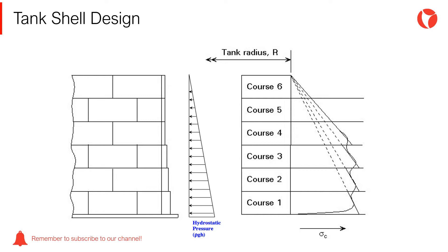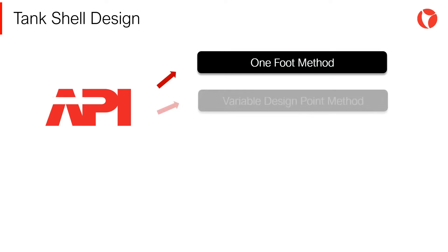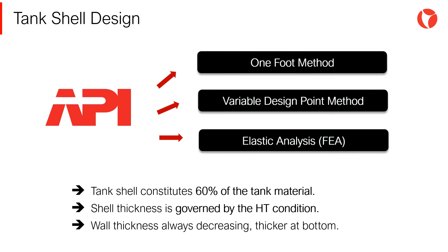In order to establish the tank shell thickness, the different calculation methods define the height at which the maximum stresses are located in every shell course — stresses that must be lower than the allowables. There are three methods to determine the tank shell thickness accepted by the storage tanks standard API 650: the 1-foot method, the variable design point method, and the elastic analysis — in other words, finite element analysis.